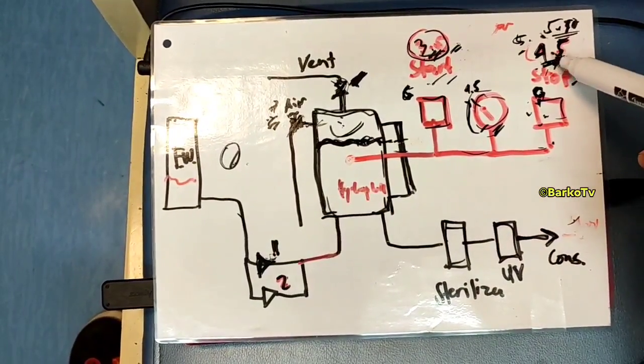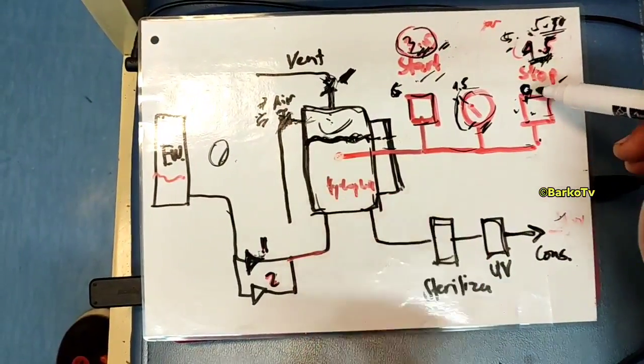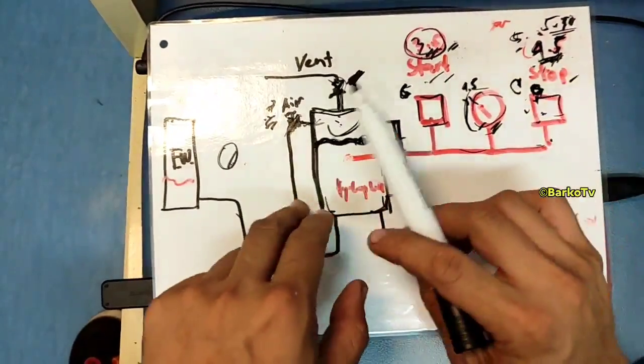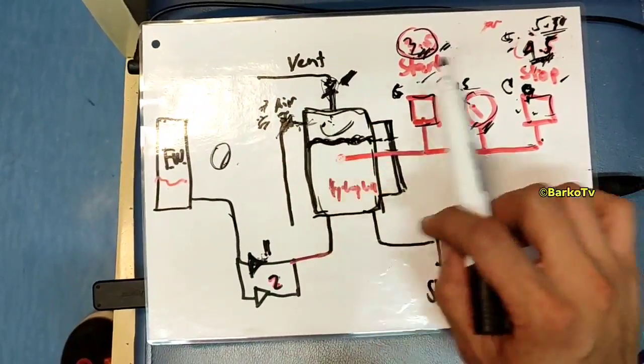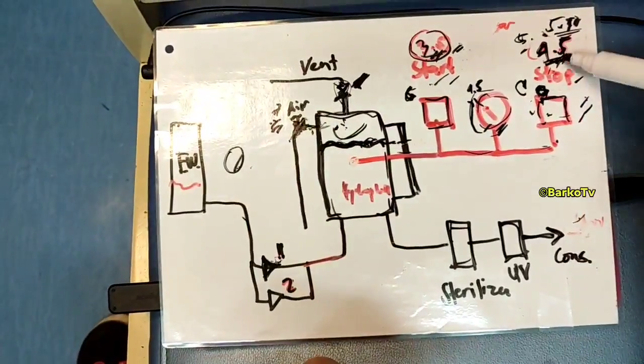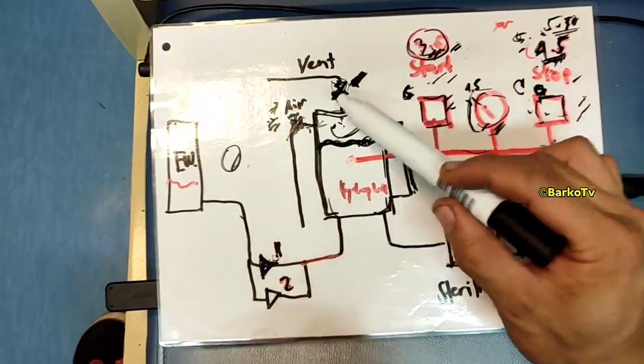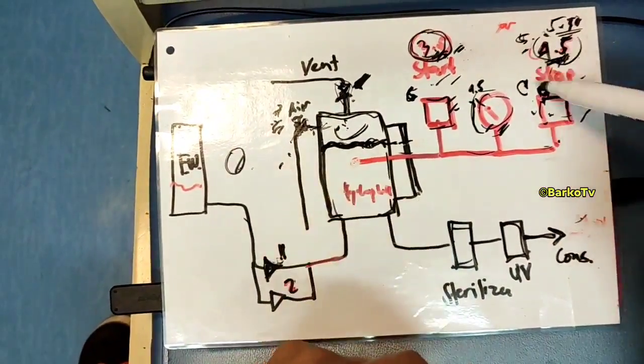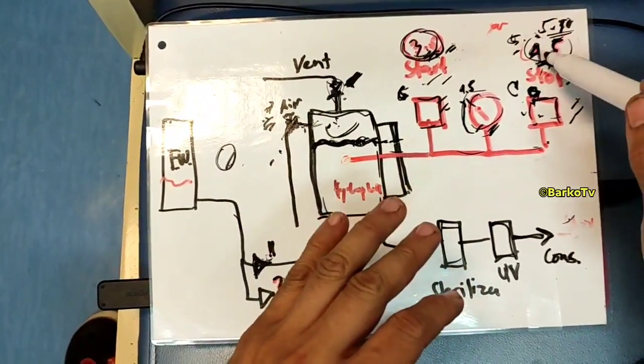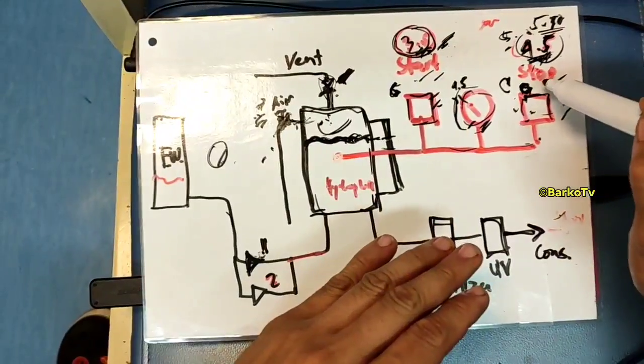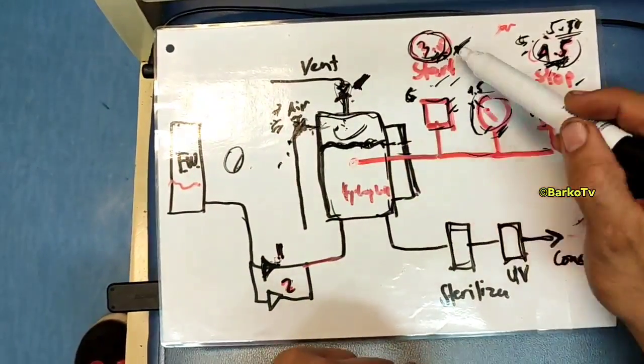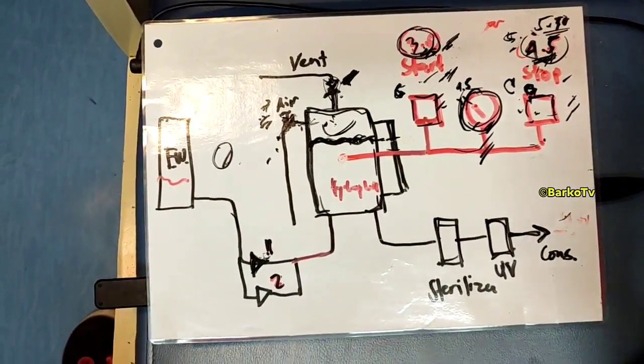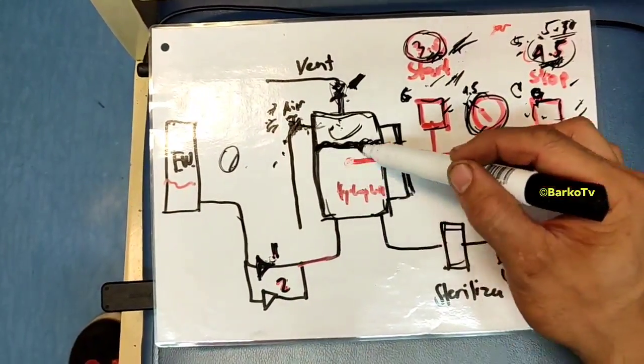Once you hit the correct setting, stop adjusting and maintain it. To simulate easily: vent to decrease pressure, feed air to increase pressure — vent and feed air so you can check and adjust the stop pressure switch. For the start pressure switch, vent air to decrease pressure and add air to increase. Make sure your gauge is correct and working.